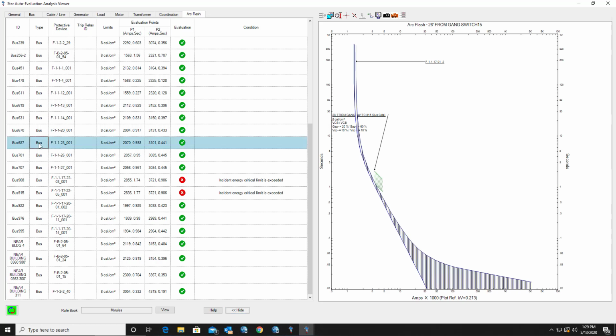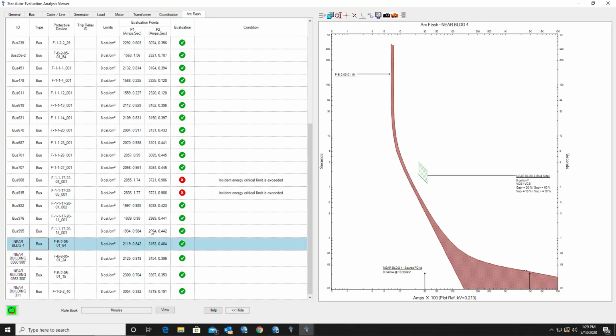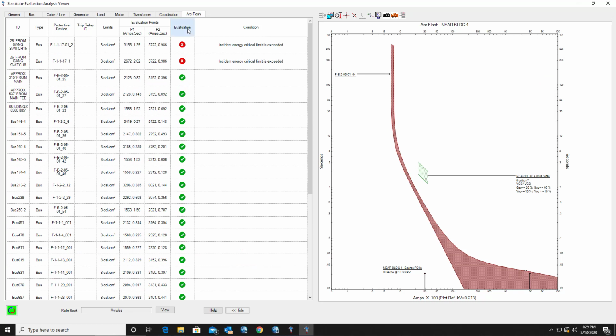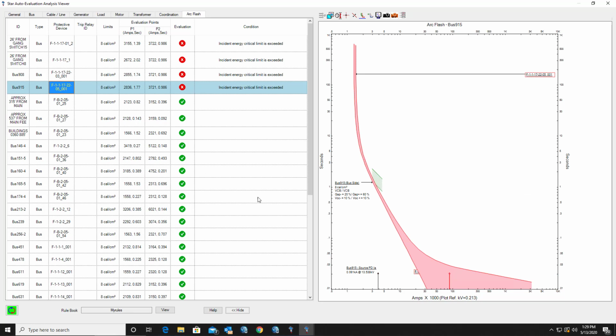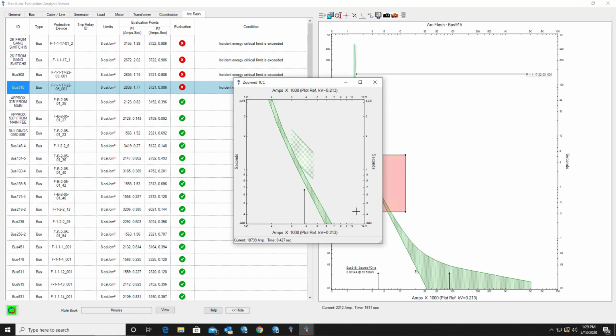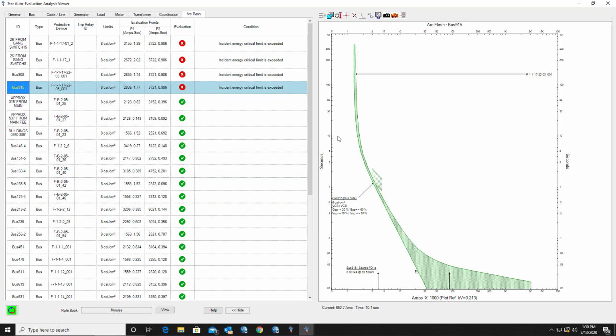So we can quickly inspect some of those locations, 8 calories, 4 calories, and so on and so forth. So now we see that only a few selected locations exceed the 8 calories, but in fact, as we can see in this region here, they do not exceed it by a significant margin. So it is expected maybe 8.5, 9 calories in some locations, but for the majority of the locations, it will be 8 calories or less.